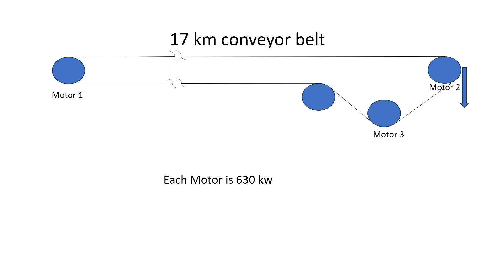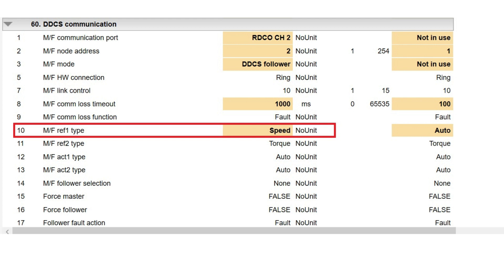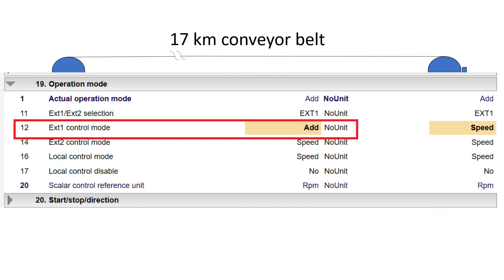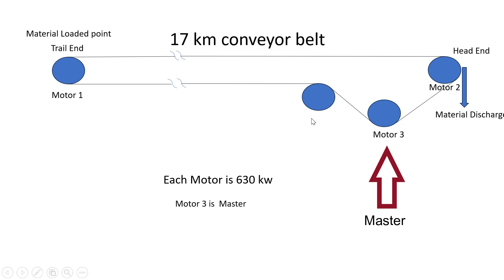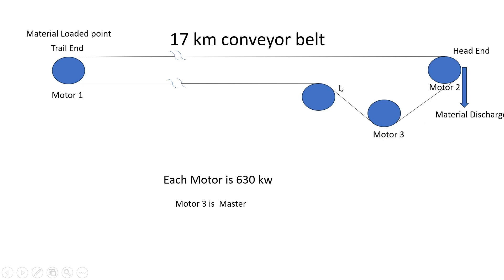Add mode is the mode that runs by both speed plus torque control combined. In Master-Follower mode — whether torque, speed, or add — in all cases the speed set point comes from the DCS to only one motor, which is called the Master. The Master motor shares the speed to the others. Here our master is Motor 3, and Motor 1 and Motor 2 are in Follower mode. Speed comes from the DCS to Motor 3, which then distributes torque and speed to Motor 2 and Motor 1.